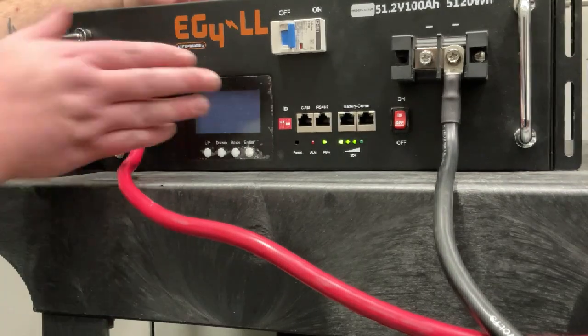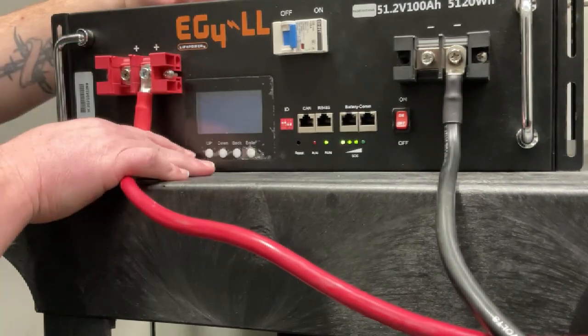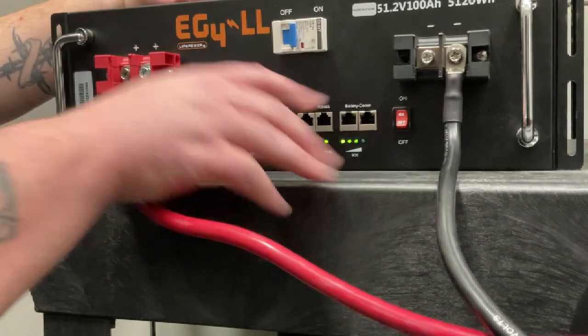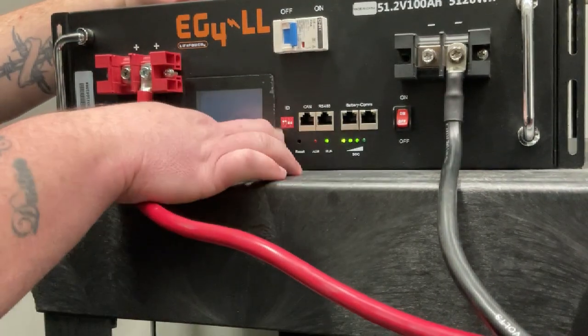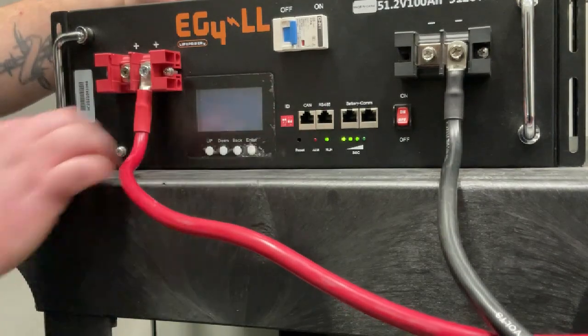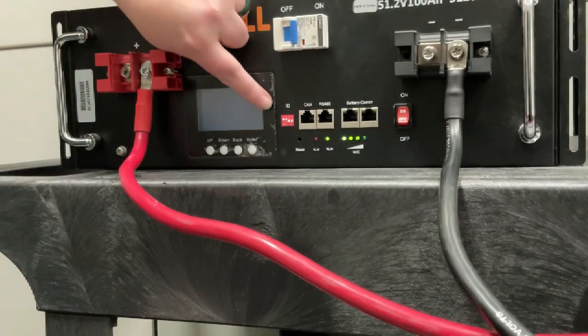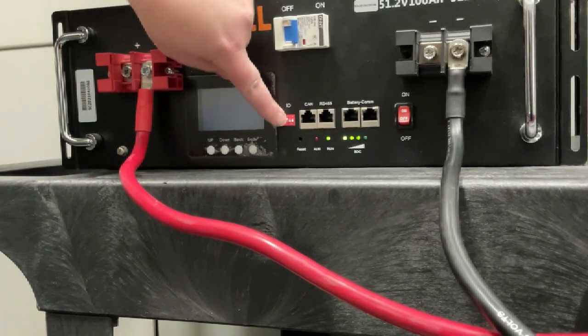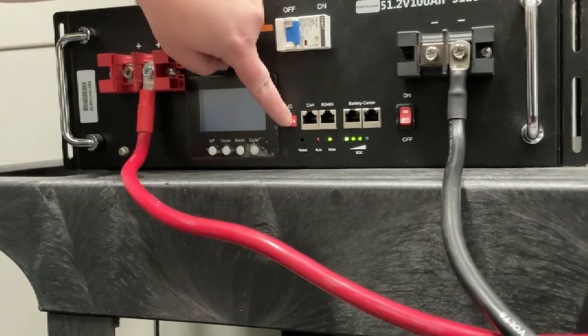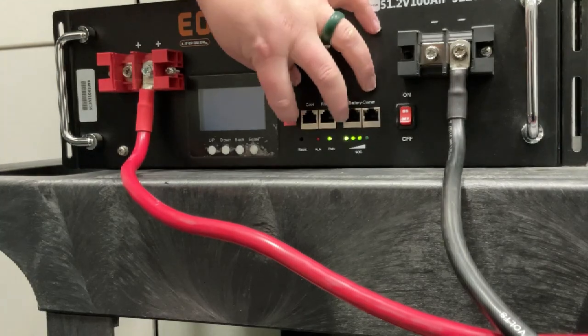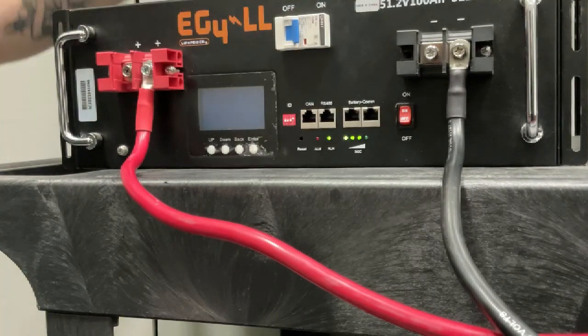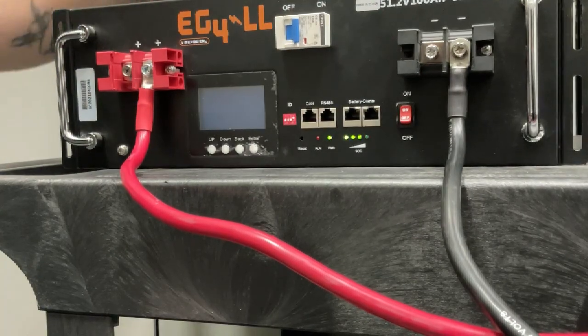In order for your EG4LL battery to communicate with your Growatt inverter, this dip switch setting needs to be down, down, down, and the fourth switch needs to be up.